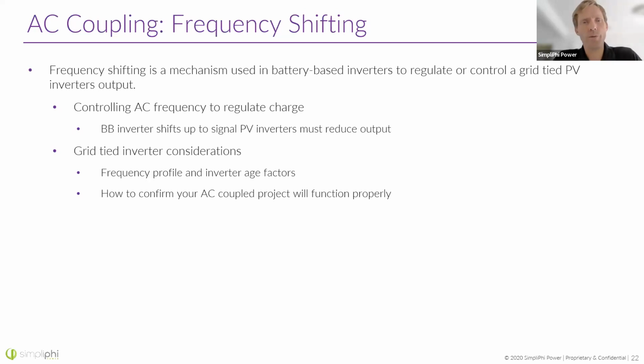Daniel, could you talk a little bit more about frequency shifting and how that's used to regulate panels? Yeah, of course, Nathan. A lot of grid-tied string inverters are looking at the frequency of the grid. With a charge controller, it's easy to shut off the flow of energy into the batteries. But with a string inverter, when the batteries are full and we can't feed back to grid, we have to somehow curtail the AC charging. And how we do that is by adjusting the frequency of the AC sine wave. The microinverters or grid-tied inverter recognize that shift and then can start to curtail their charging rate.